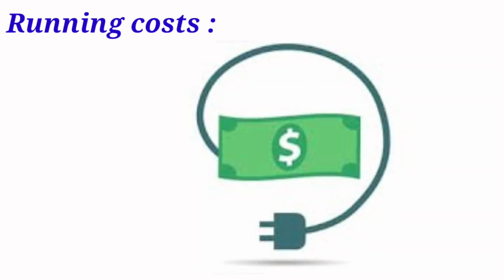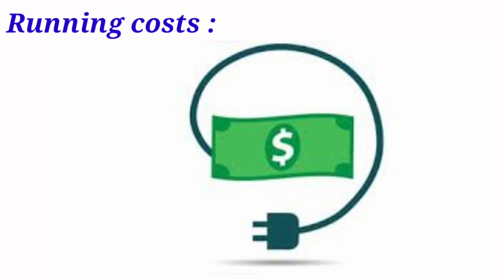Running costs. The age and condition of FCU systems will significantly affect running costs. Older systems tend to have higher rates of temperature controller failure, poorly operating valves and inefficient central plant, all of which can increase costs. As with all systems, efficiency will be improved by good management and commissioning, especially in relation to the calibration of temperature sensors and the maintenance of valves. A building management system, BMS, will provide a higher level of control and, if well managed, will help reduce running costs.